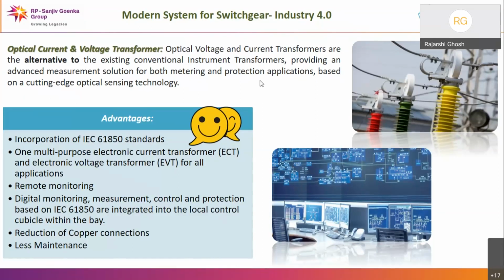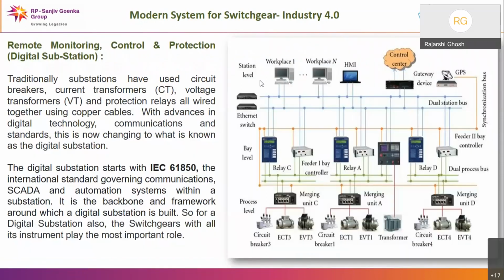Digital monitoring, measurement, control, and protection based on IEC 61850 are integrated into the local control cubicle within the bay. This reduces the copper connections, requires less maintenance, and reduces the cost. With the concept of this modern digital substation, we can reduce the multi-core copper wirings to a great extent with the IEC 61850 communication backbone.